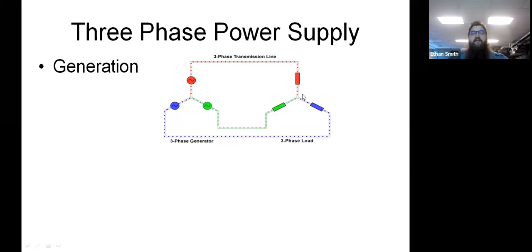But where we have a three-phase load, we're simply taking power directly from the grid and pumping it right into the loads. Okay. In fact, there's probably 3-phase power in your residential neighborhood. This is how they transmit power to the point of use typically. It usually gets converted in a neighborhood transformer station and then pumped into houses as two phases instead of 3. And they balance the load between all 3 phases in the residential market. Okay. But in the commercial world, 3-phase is king.